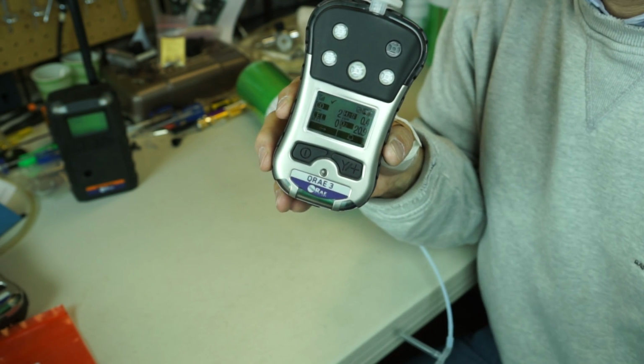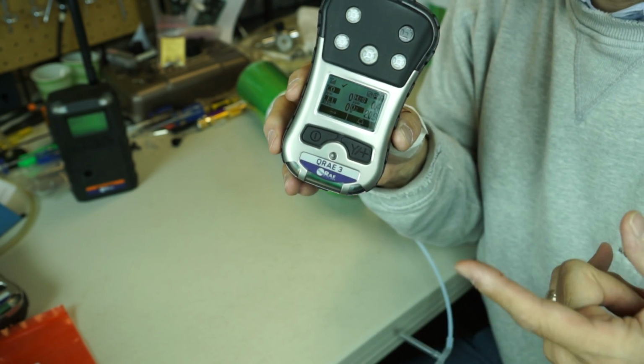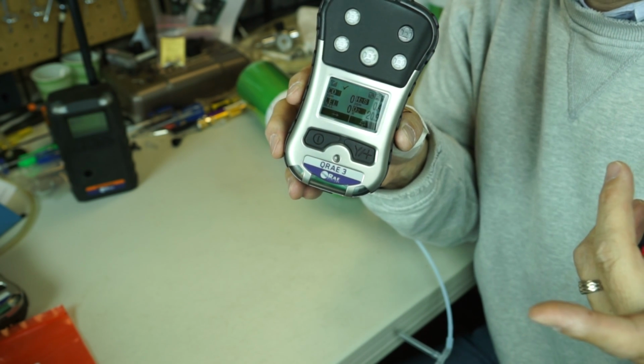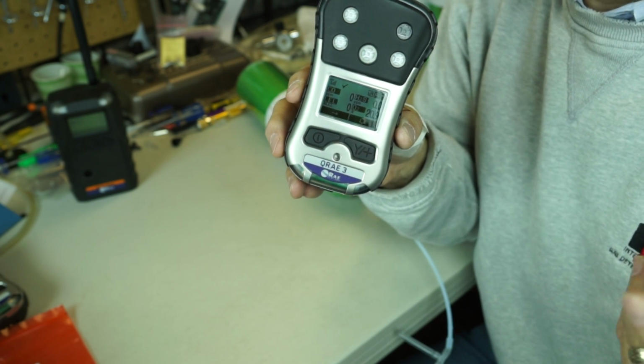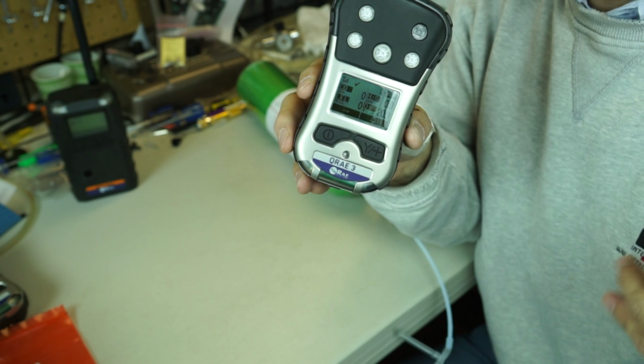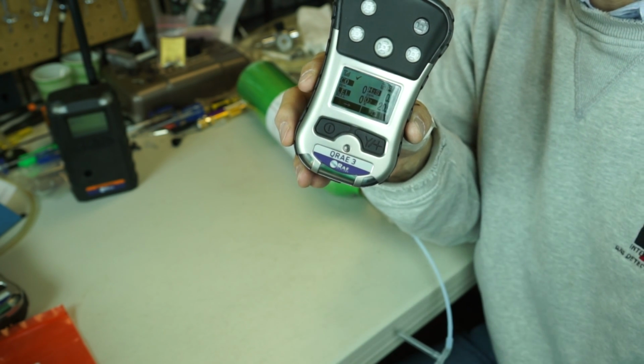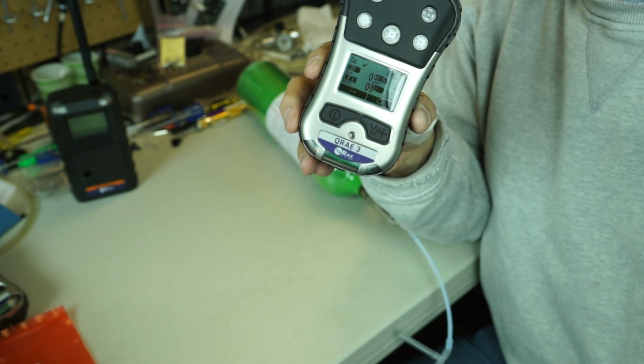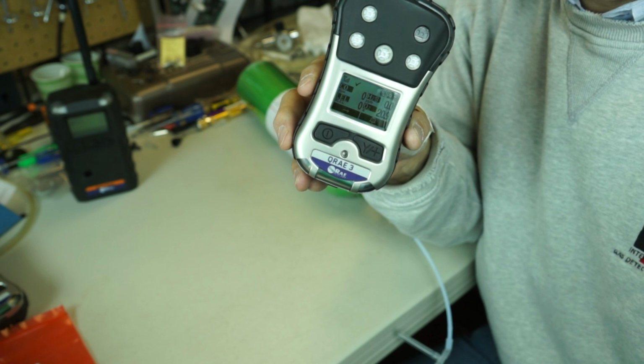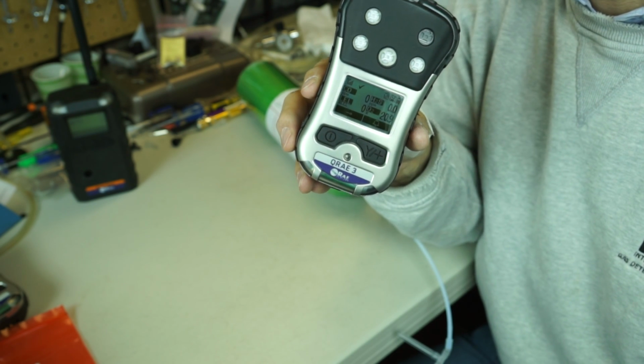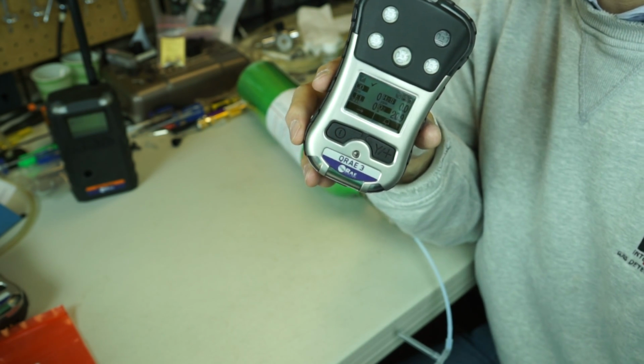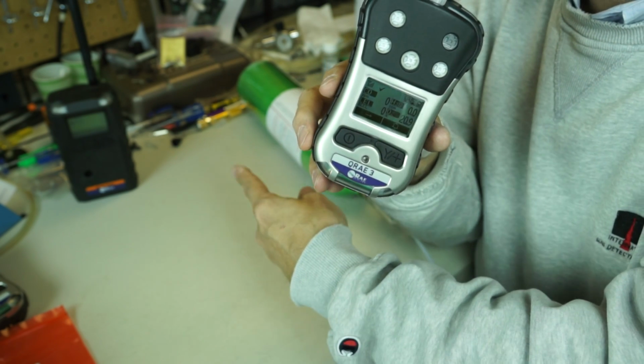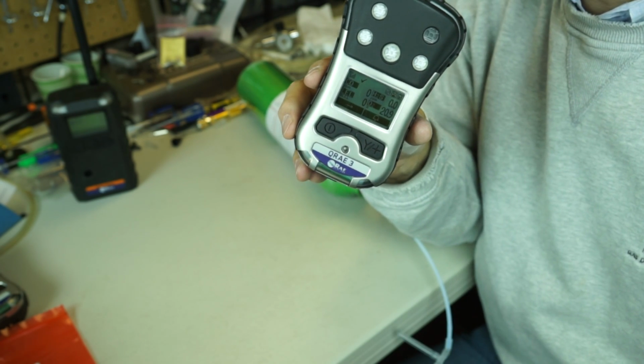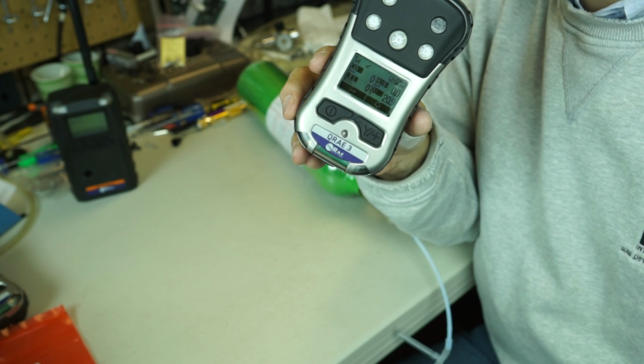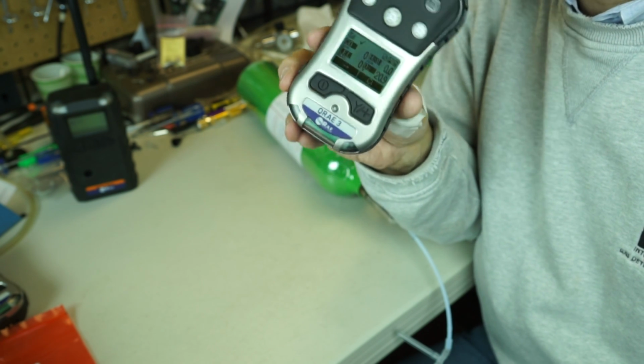So what I've showed you here is how to calibrate using the T that comes with the instrument. I've also showed you how simple it is to calibrate. I've also showed you a post bump. Post bump is all we're doing is giving it the same gas we use to calibrate, in normal operation mode, just to make sure that we didn't screw up and everything is working right. And as an added bonus, you got to hear my echo view go off in the background, which is the wireless device that sees gas detectors up to, in this case, 600 feet.